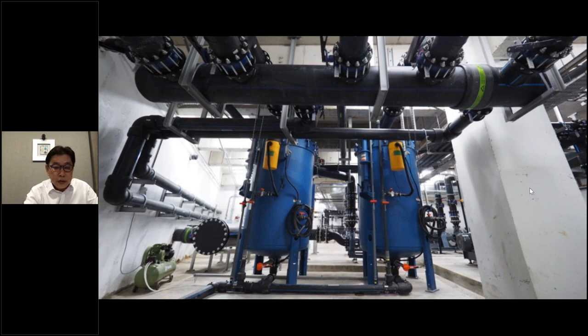So the horizontal filter, tackling all these control valves, you need one team to be dedicated, to make sure they know what they're doing. And there are so many parts, valves, manifolds, a lot of things for you to handle. Then you switch the pump off and on a couple of times for backwash and for rinse, and you have to go to the drain and check whether the backwash water came out clear before you can go back in. There's a lot of hassle.